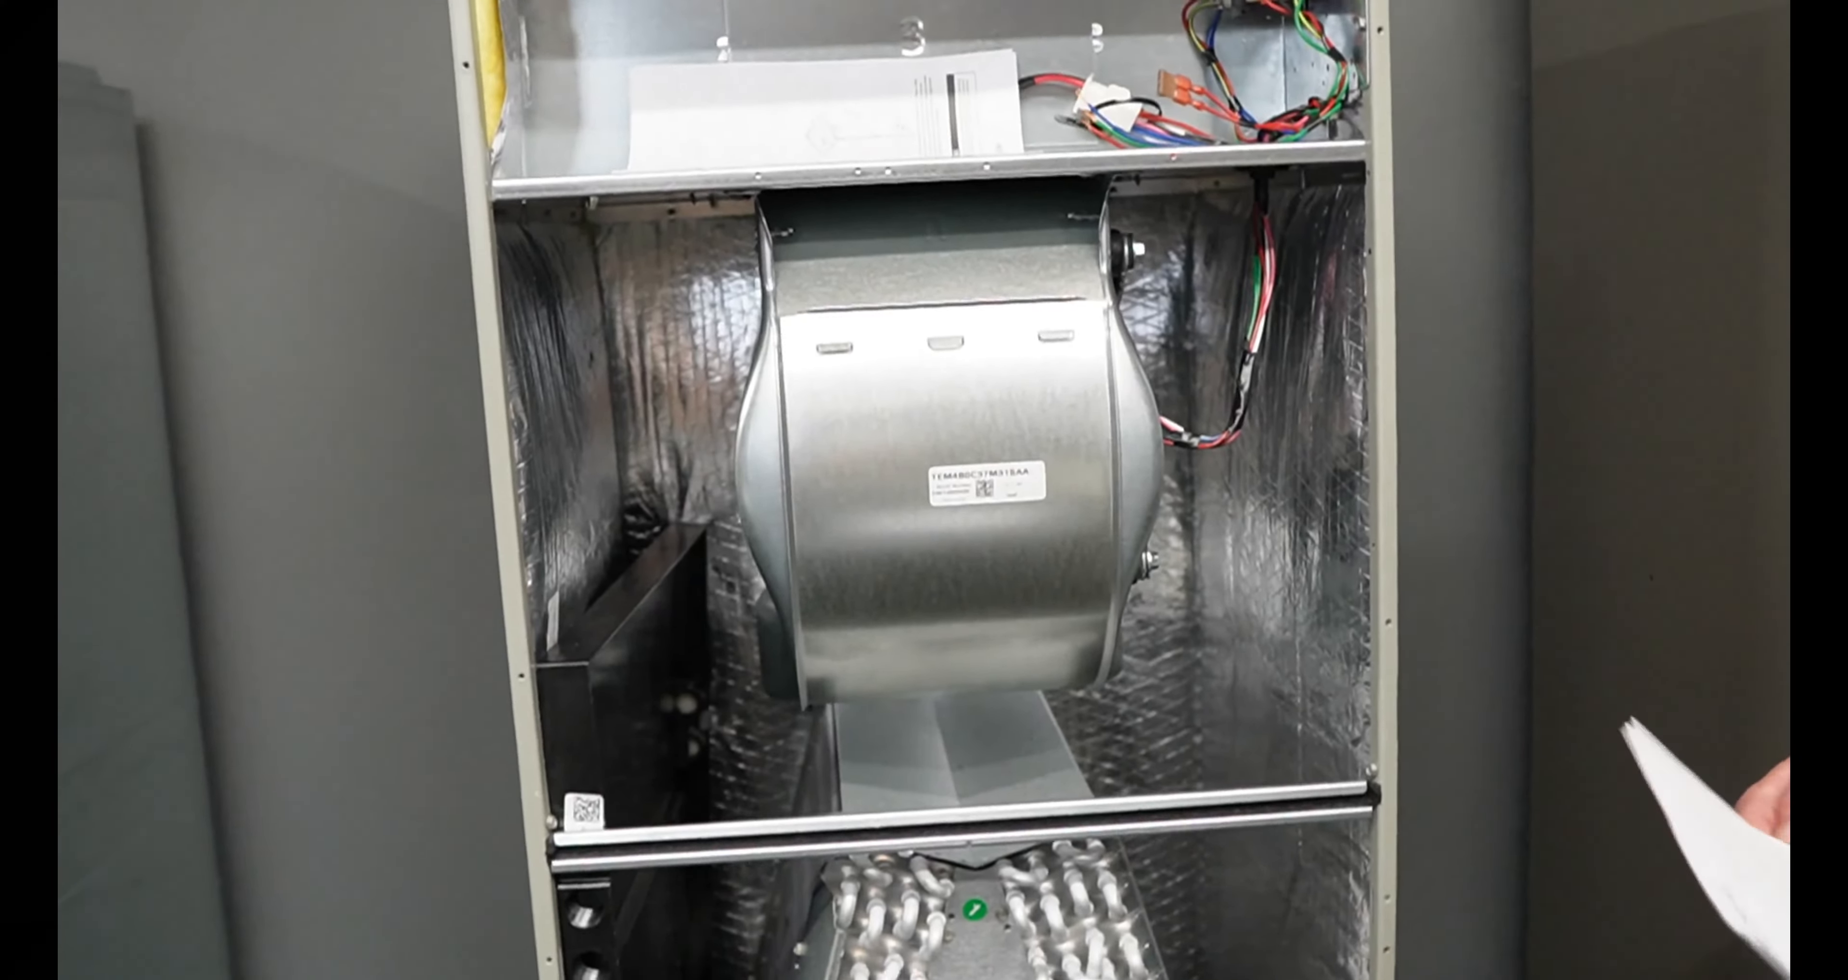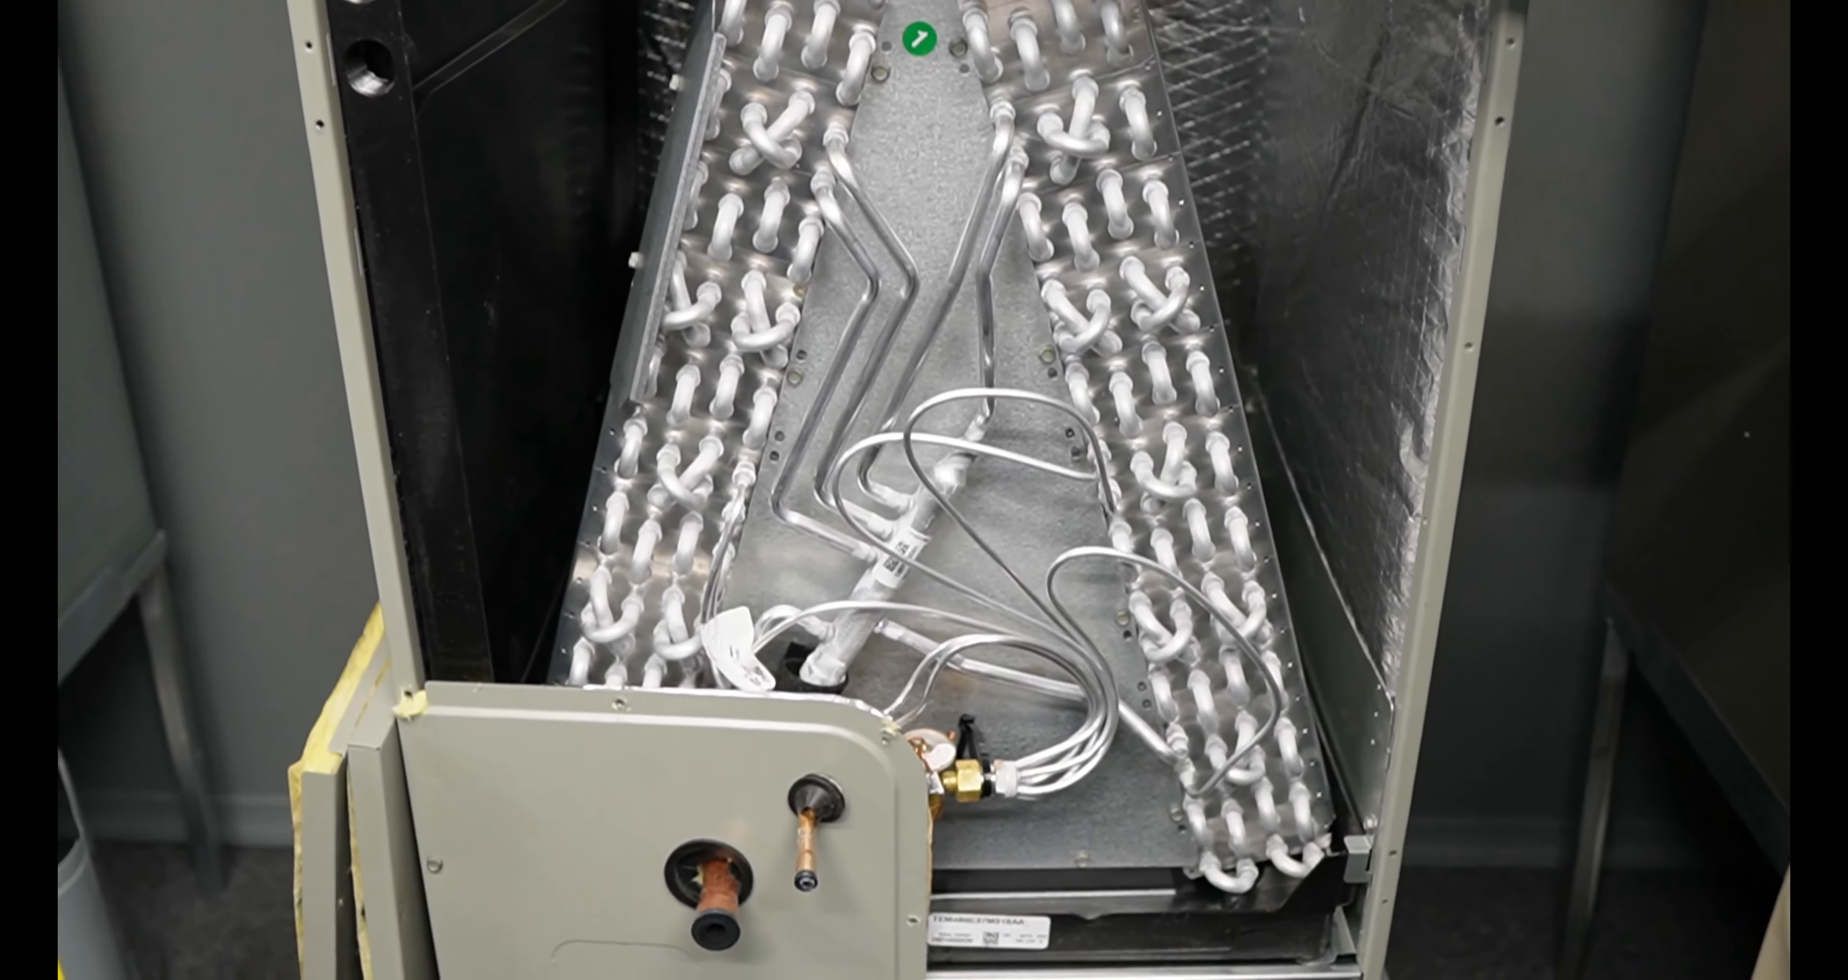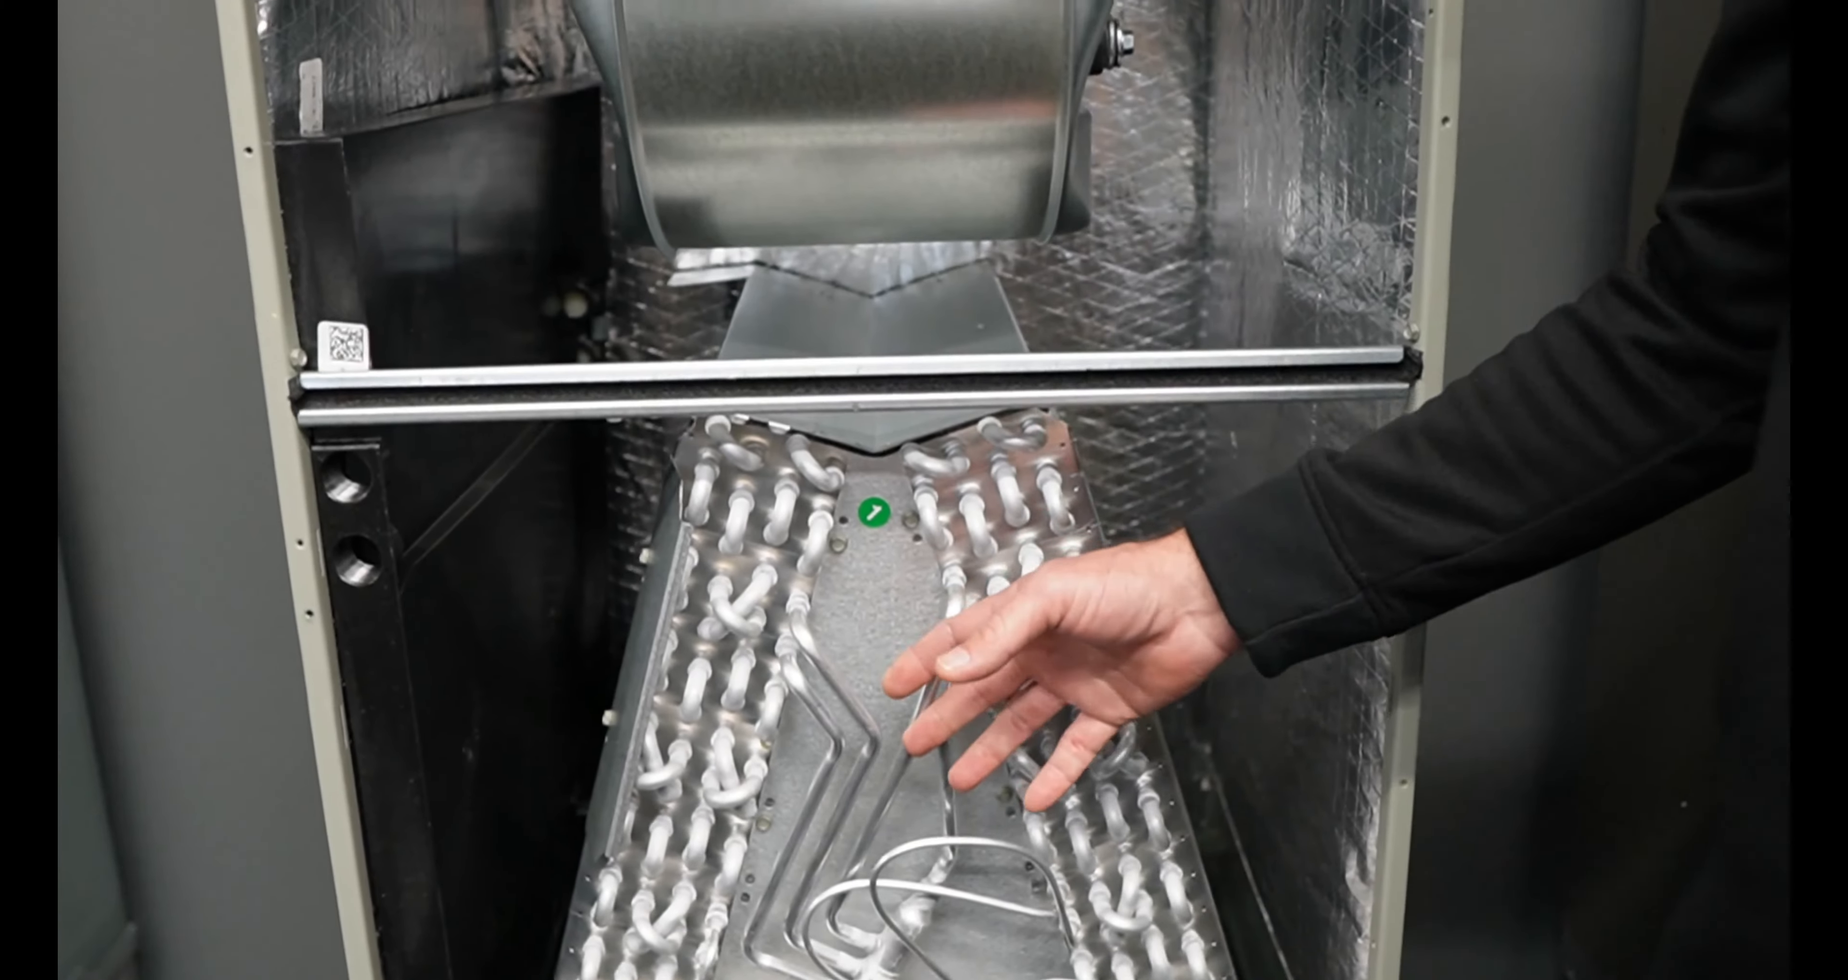Take a look at that coil right there. So let's look at this coil. It's got 10 millimeter tubes here, four rows, 20 something inches tall. So the reason for this is because volume of refrigerant. This condenser has those 3/8 tube coils there that holds a lot of refrigerant. So it's got to be pumped into this evaporator here and for heat pumps too. It's going to be used for heat pumps too. Absolutely. Unbelievable.